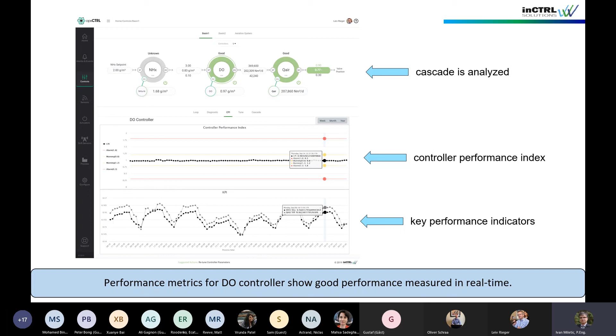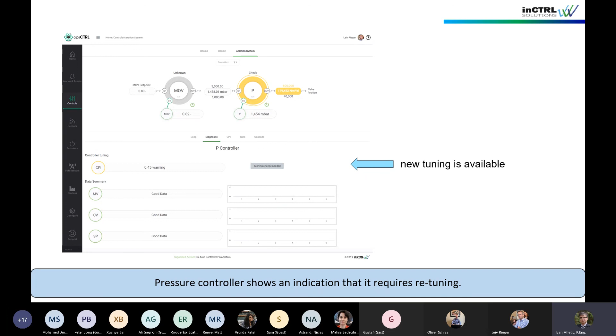In this case, this pressure controller shows a warning, but notice that all the input data into the algorithm - the manipulated and controlled variables and the set point - seem to be in good condition, which allows the algorithm to process the data and provide new tuning suggestions for this controller.